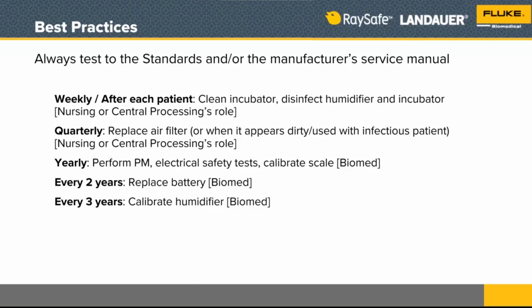We're also going to look at those as biomeds when we do the preventive maintenance testing. And this is typically going to be once a year that we look at these infant incubators. We're going to do electrical safety tests as well. And we may calibrate the scale if there's one included in the incubator. About every 2 years, we're going to replace the battery, no matter what the battery chemistry is, because we don't want the battery to fail just when it's needed the most. And that's going to be most important for those transport incubators. Every 3 years, we're going to calibrate the humidifier, depending on what kind of humidifier is included.